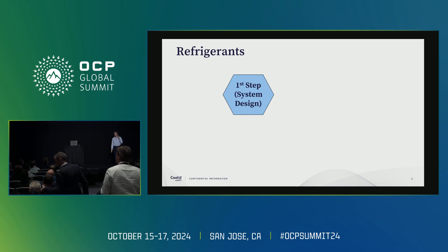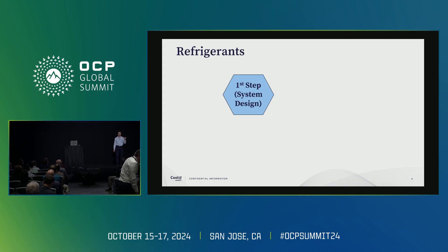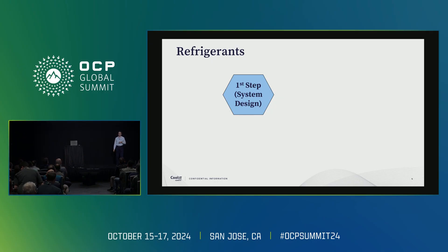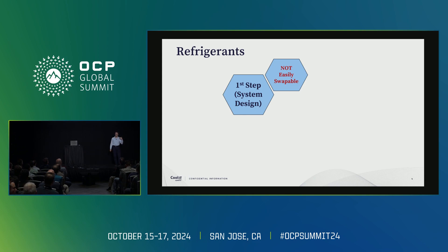The first and most important thing about two-phase system design is to first select your refrigerant — that is where everyone needs to start. You have to decide: I'm going to use R515B or R1234YF. That is the first block you need to set, then build your whole system based on that. After you've done that, it is not easily swappable. If you select your refrigerant, you cannot come back mid-project and say, let's change the refrigerant. There are several factors involved; it is not easy to do.